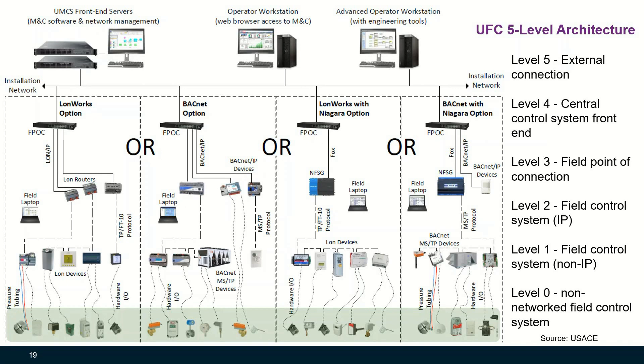In this UFC five-level HVAC control system architecture: Level one, field control system non-IP network, is equivalent to the field control network discussed earlier. Level two, field control system IP network, is equivalent to the building control network discussed earlier. Level three, field point of connection devices, provides an additional layer of security protection for the building automation system.